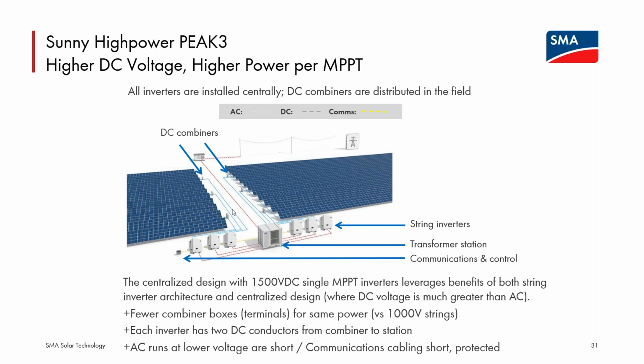They'll be from the combiner box, the positive and negative. You have at least 3 conductors on the AC side; have those be as short as possible, to save conductor cost and save losses. Having them located centrally also provides very easy wiring of communications. Like you said, if the site has already been laid out and somebody forgot to accommodate the communications cabling, it's very simple to accommodate after the fact if all of these inverters are located in only a few spots throughout the plant. Whereas if they're scattered throughout the array field, it becomes much harder to go back and trench out additional conduit runs.